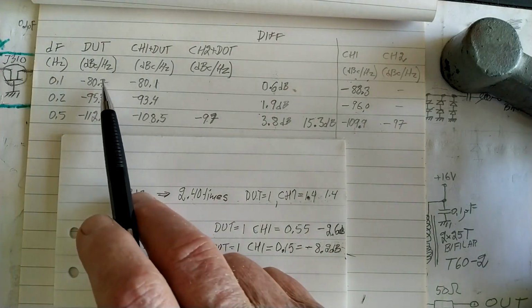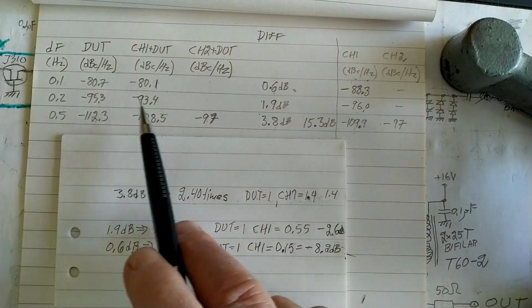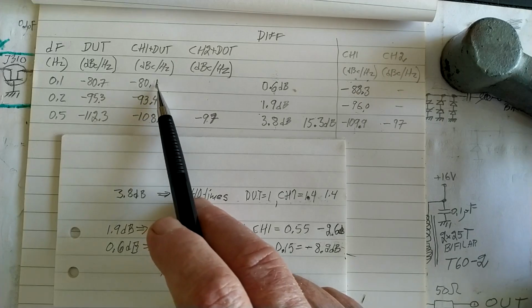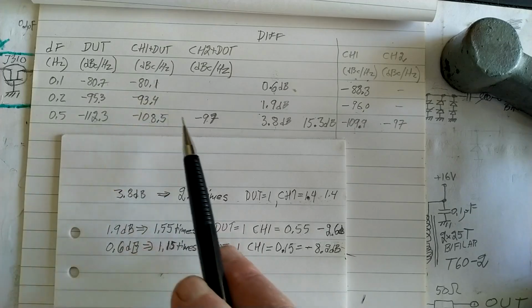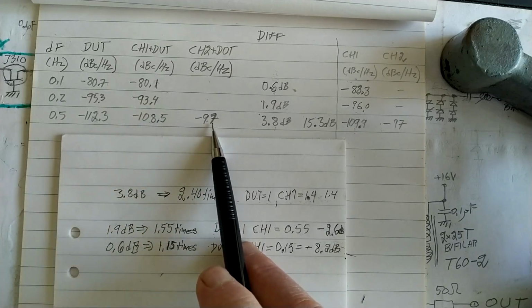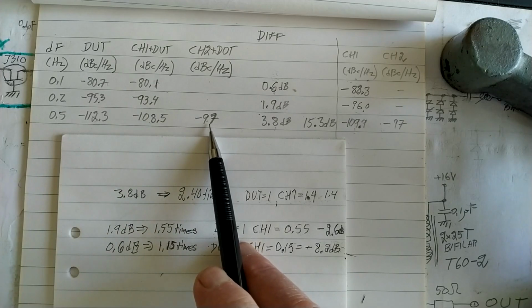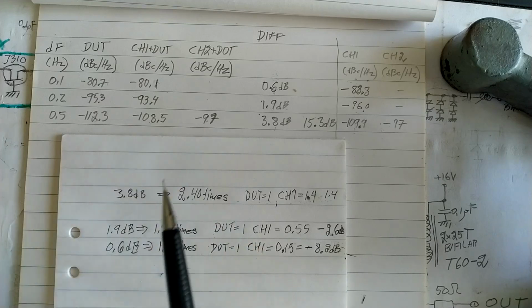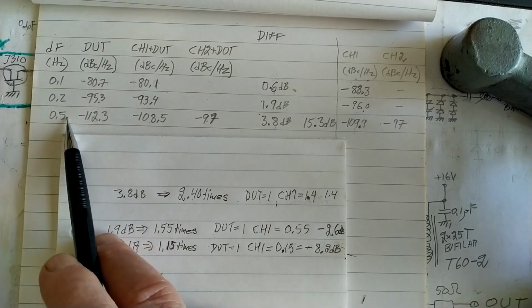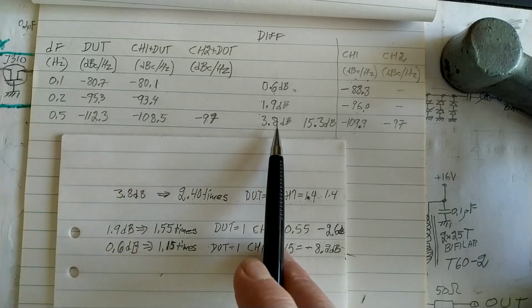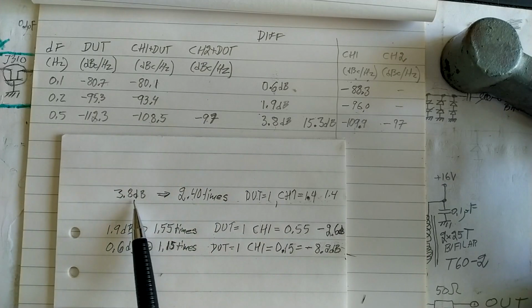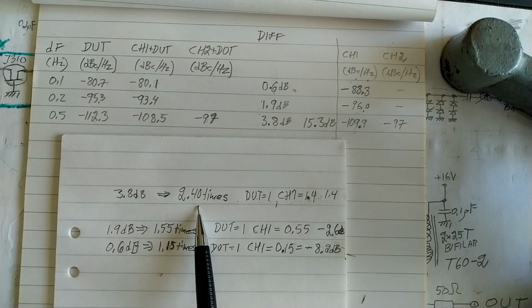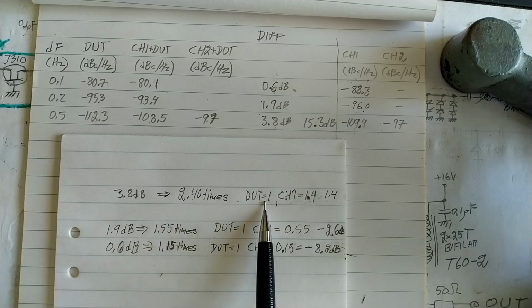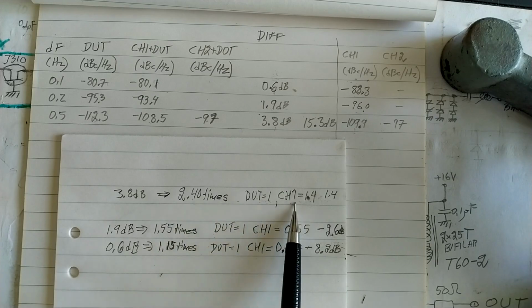I have these values for the device under test, correlation spectra, and for channel 1 reference oscillator plus the device under test, that was the green curve, and 97 decibels at 0.5 Hz for the device under test plus the channel 2 reference oscillator. At 0.5 Hz, there was a 3.8 dB difference between this and that. 3.8 dB, that is 2.4 times. That means that the device under test is one unit of noise, while channel 1 reference oscillator is 1.4.